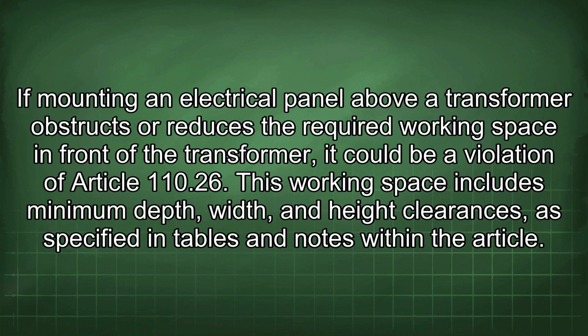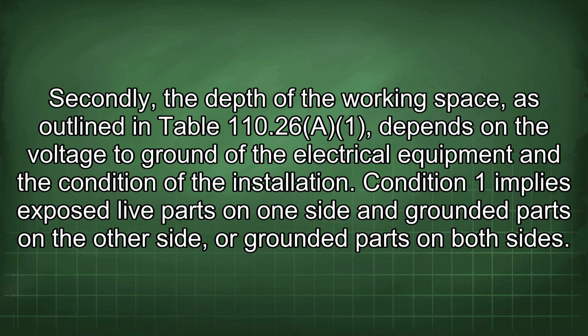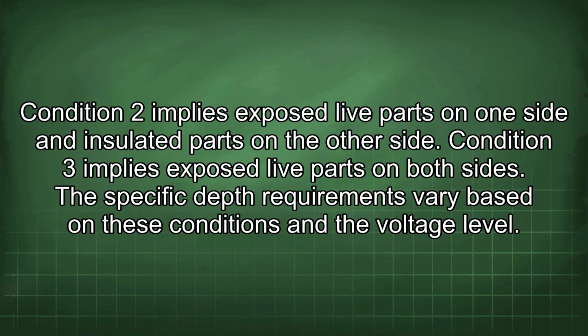If mounting an electrical panel above a transformer obstructs or reduces the required working space in front of the transformer, it could be a violation of Article 110.26. This working space includes minimum depth, width, and height clearances, as specified in tables and notes within the article. Secondly, the depth of the working space, as outlined in Table 110.26(A), depends on the voltage to ground of the electrical equipment and the condition of the installation. Condition 1 implies exposed live parts on one side and grounded parts on the other side, or grounded parts on both sides. Condition 2 implies exposed live parts on one side and insulated parts on the other side. Condition 3 implies exposed live parts on both sides.